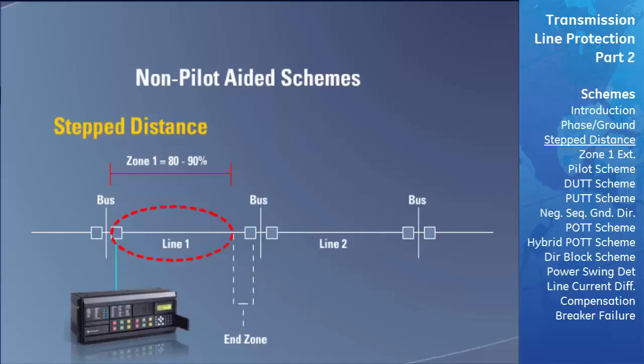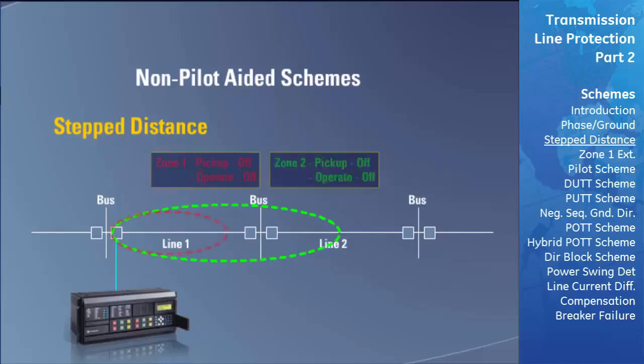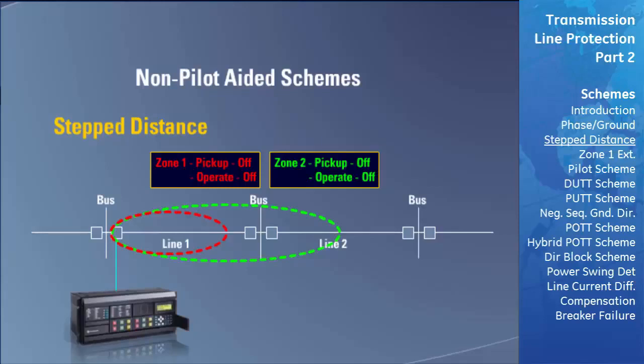The second zone of protection is set to overreach and extends from the beginning of the transmission line past its end and into the next adjoining line. Zone 2 is usually set to 120 percent of the impedance of the transmission line so it can detect faults in the end zone area that zone 1 cannot detect. Zone 2 is always programmed to have a time delay set between 0.25 and 0.4 seconds. Together, zone 1 and zone 2 have the ability to protect the entire length of the transmission line.